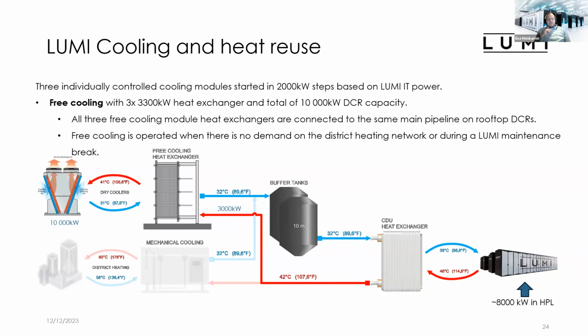So then last we have this free cooling when we are bypassing the heat pumps and putting all waste heat from the Lumi to the outside. And this is only operated when there is no demand on the district heating network, or when we have a maintenance break ongoing with the Lumi, when we cannot guarantee that we have enough load all the time for these heat pumps to operate. I will get a more detailed presentation tomorrow about this heat reuse, how it's operated and how it has been implemented in the Lumi.